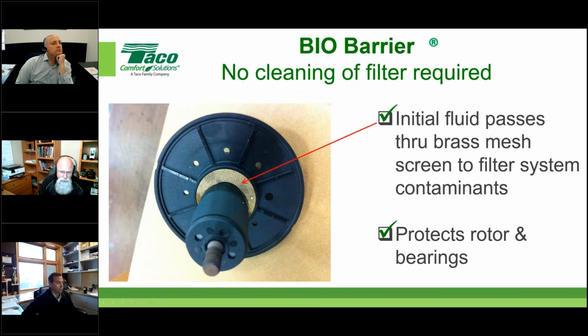Okay, here's the back side of it, and here's the actual motor. Here's the electronically commutated motor, the ECM. Notice that back underneath this is where the fluid would come through and do the two things the fluid does for a wet rotor circulator. It gives us cooling, and it gives us lubrication on these shafts. So the shafts are lubricated and the motor itself is cooled with the fluid. So we want to make sure the fluid is nice and clean, at least on the initial startup or commissioning of the system. So again, it protects and does what it's supposed to do.